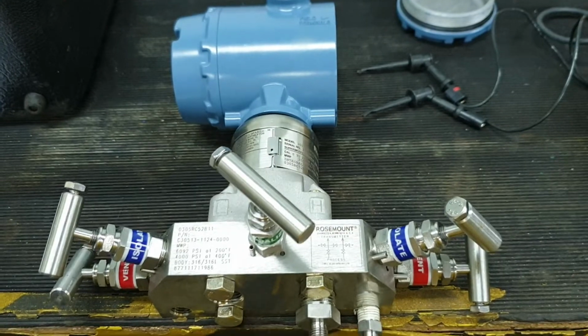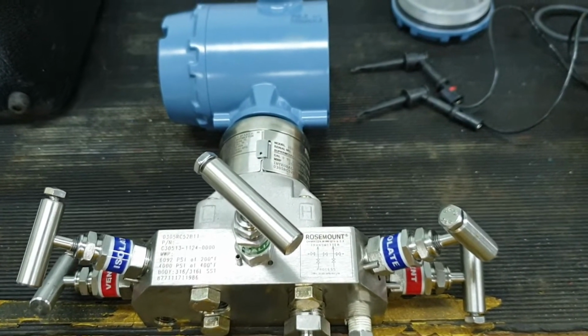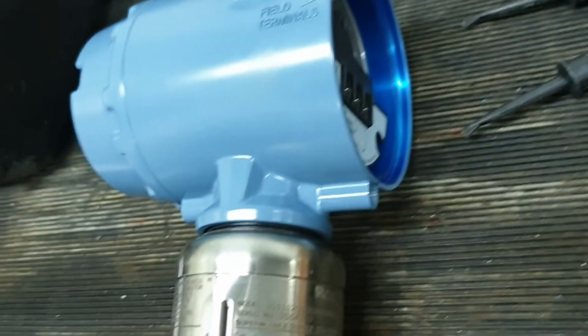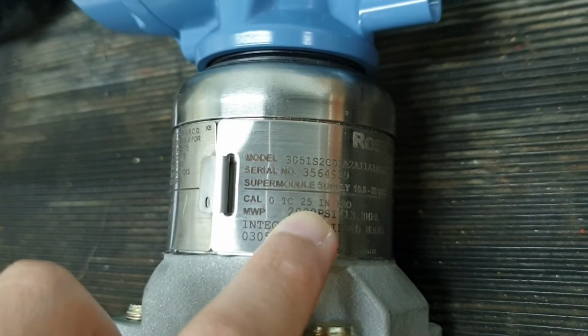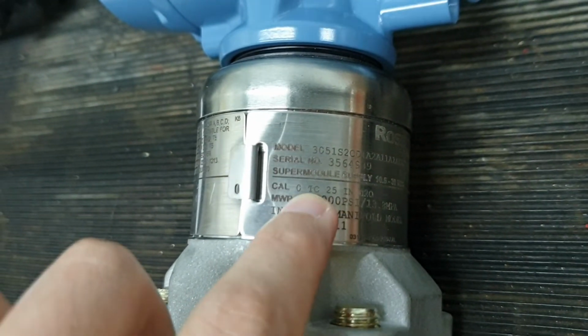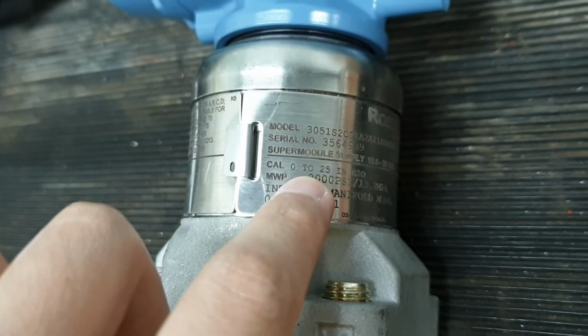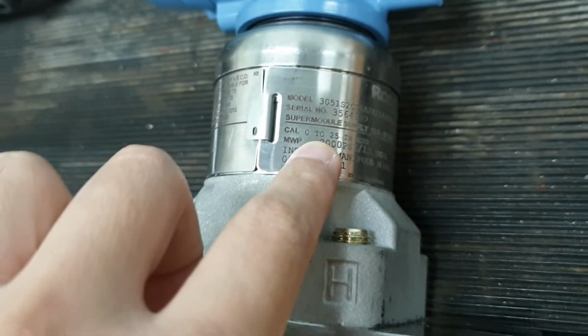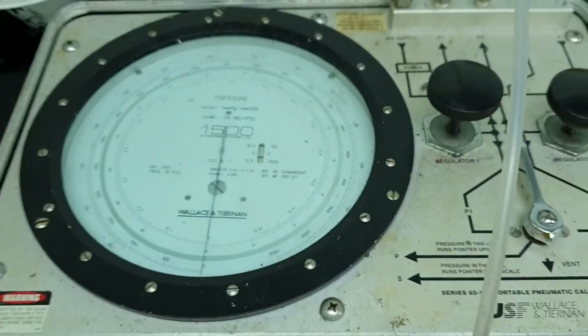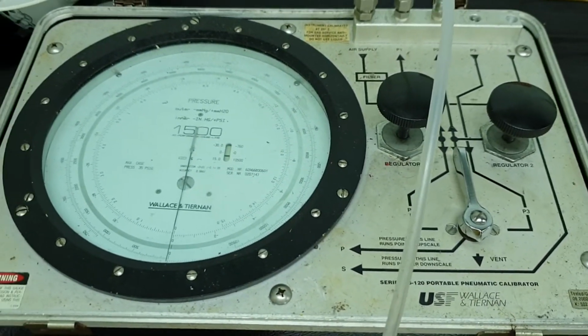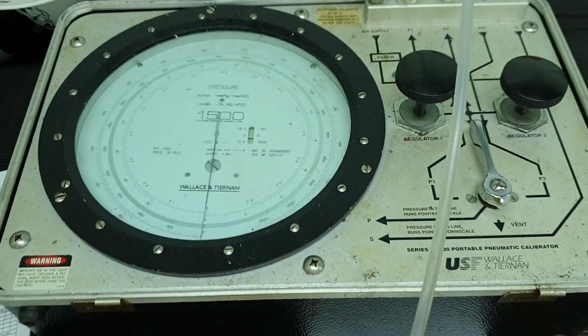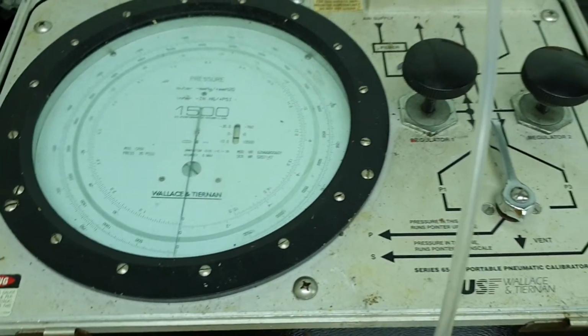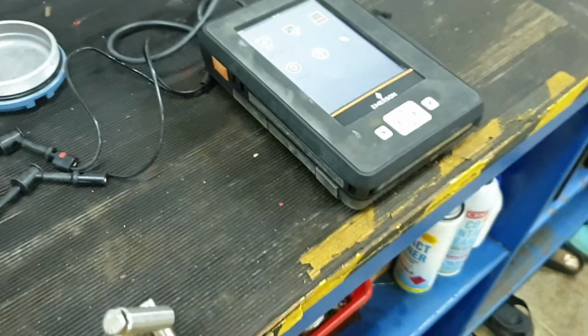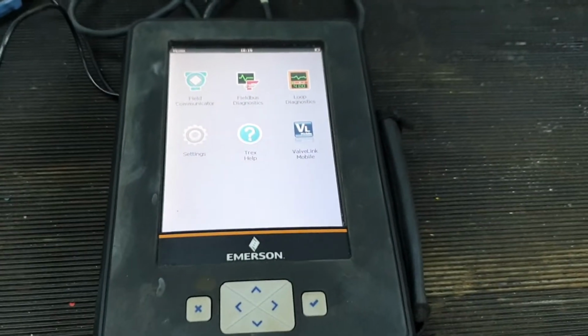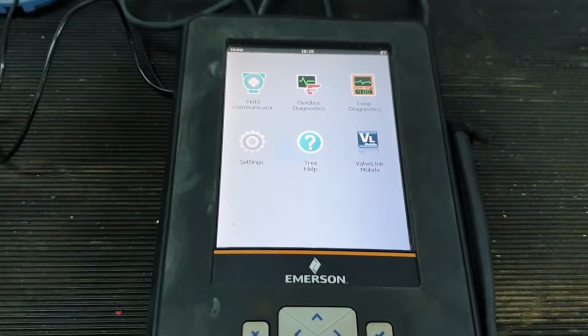Firstly, we're going to ensure that our transmitter is within the range, so that we know what kind of pressure we want to inject into our transmitter. So this is our portable pneumatic calibrator, and the range will be determined later on by our communicator, which is this Emerson device.